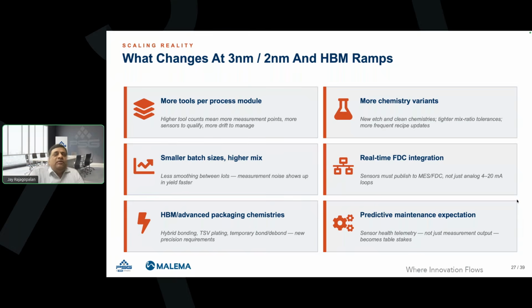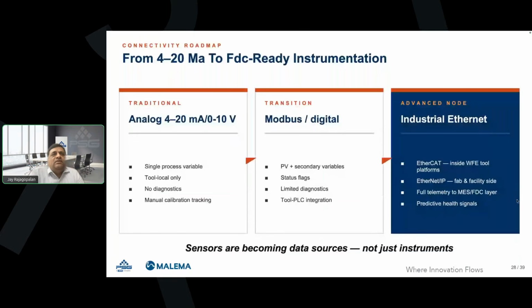So traditionally, people used 4 to 20 milliampere and 0 to 10 volts. Still, that's being used with many tool manufacturers. In between, for now, a lot of people still offer Modbus and other digital communication protocols from the devices to the tool, which enables easy integration, etc. But more advanced industrial communication protocols are now being adopted. Vendors also provide, and the OEMs also try to integrate, these advanced protocols. EtherCAT is gaining traction in a variety of tools. Ethernet IP could also be used. And there are other communication protocols also being offered. So the advantage, as I told you, is that it gives you more data, not just the flow. And that's very critical in these kind of areas. Right?